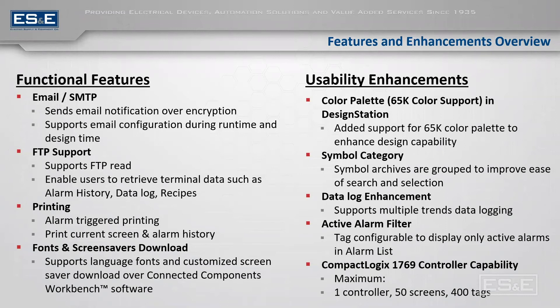They have also added the ability for the PanelView 800 to communicate with a CompactLogix 1769 controller. The PanelView allows only 50 screens, 400 tags, and just the one controller. However, it will not allow you to use the email or FTP support when communicating with a CompactLogix controller, so do keep that in mind if you intend on connecting the PanelView 800 to a CompactLogix 1769 controller.